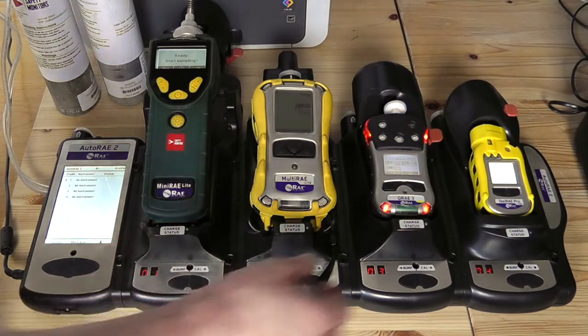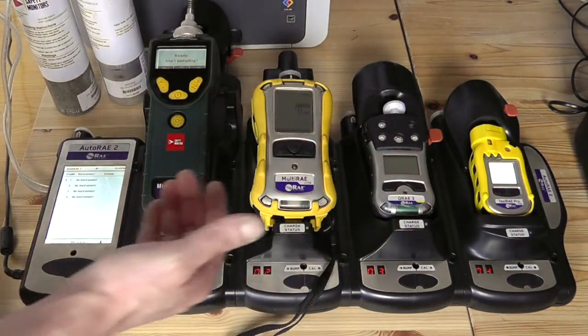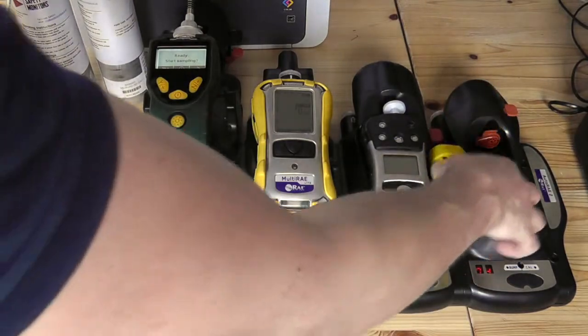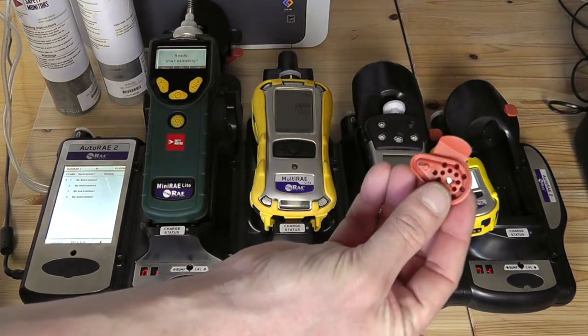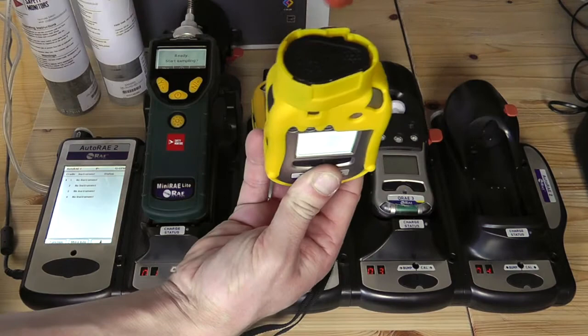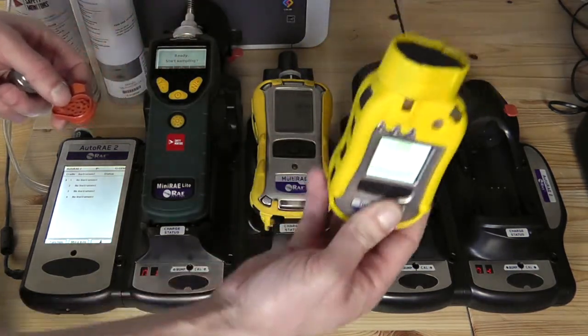Excuse me for the man down alarm. The important thing to bear in mind with some of these cradles is they all function in a very similar way. However, there are some adapters that are required. In the ToxiRAE Pro derivative, what we have installed in this particular device is a clip-in clip-out adapter. This happens to be for the ToxiRAE Pro derivative, so we can see by the top mounting on the device that this is the ToxiRAE Pro PID device.